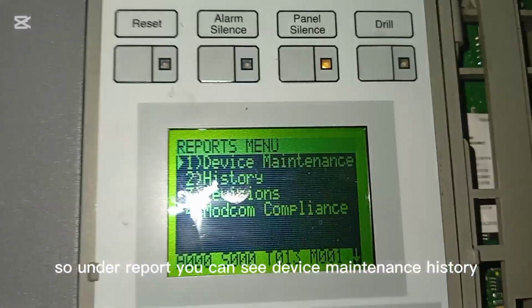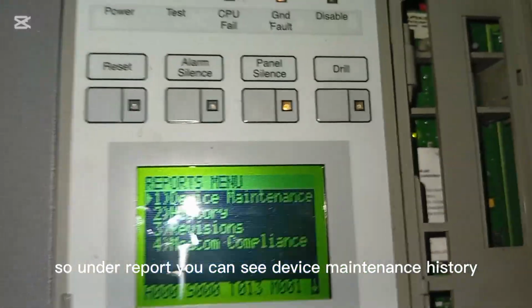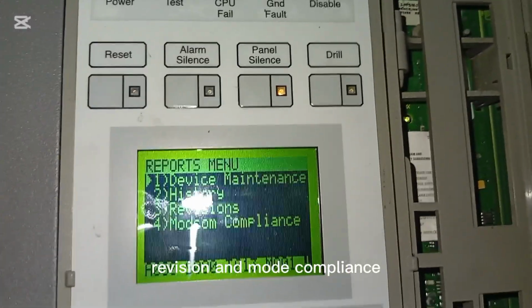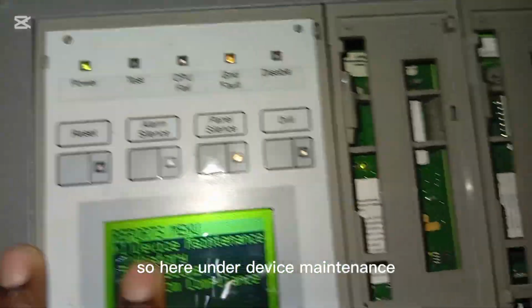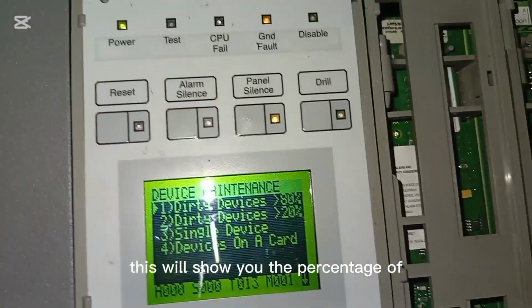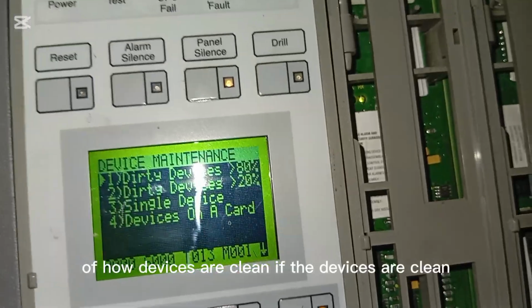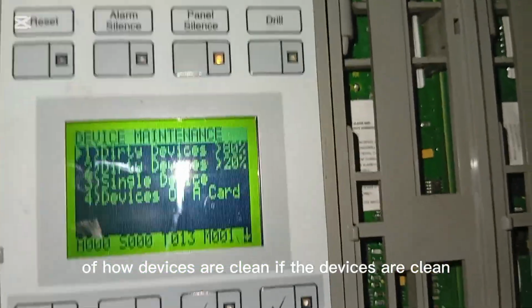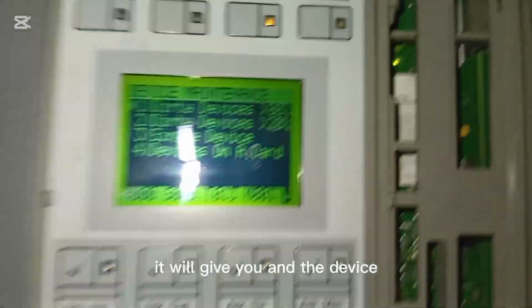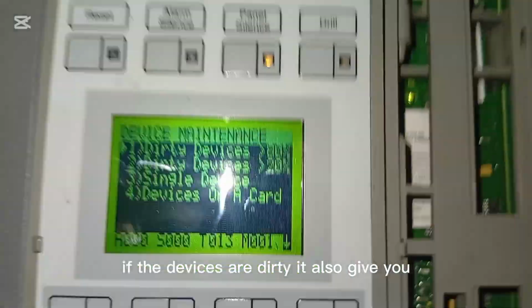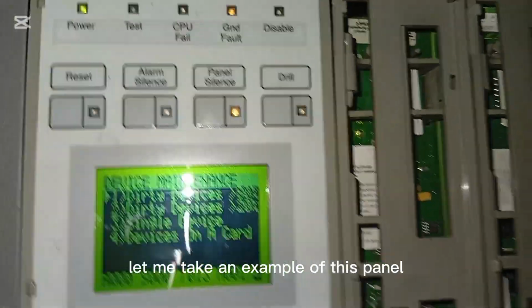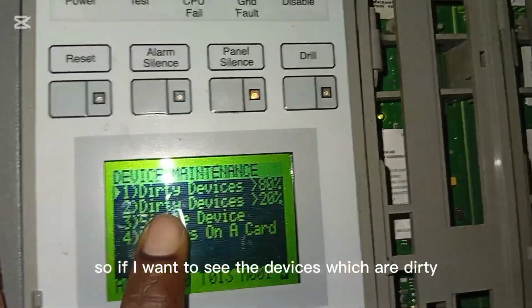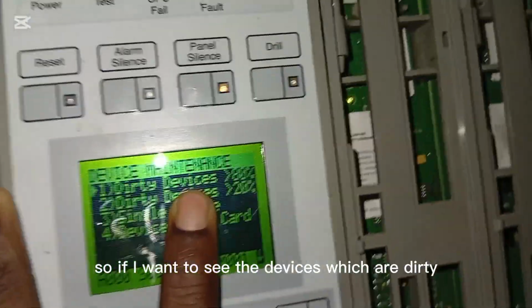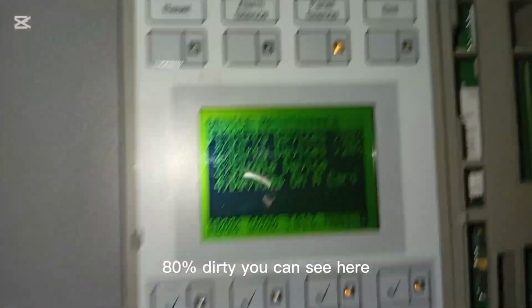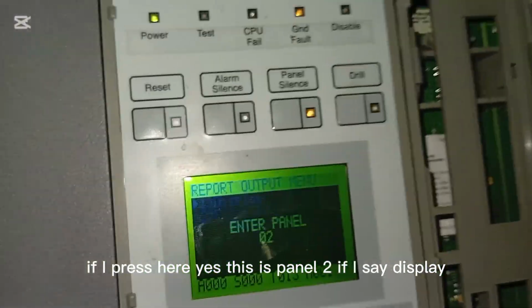Under report, you can see device maintenance, history, revision and modcom compliance. Under device maintenance, this will show you the percentage of how clean the devices are. If the devices are clean, it will tell you, and if the devices are dirty, it will also tell you. Let me take an example of this panel. If I want to see the devices which are 80% dirty, I press here, yes, this is panel 2, and I say display.